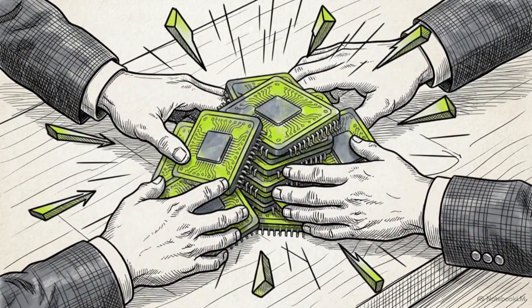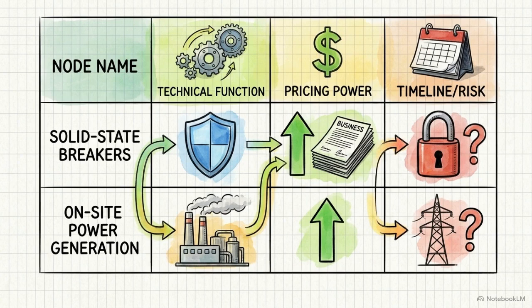Moving off the partner list, we find the infrastructure nodes. The third component is solid-state circuit breakers, located throughout the 800-volt distribution network. AI workloads create massive power swings, up to 50% of peak load within fractions of a second. These breakers are mandatory to instantly isolate those surges and protect the grid.